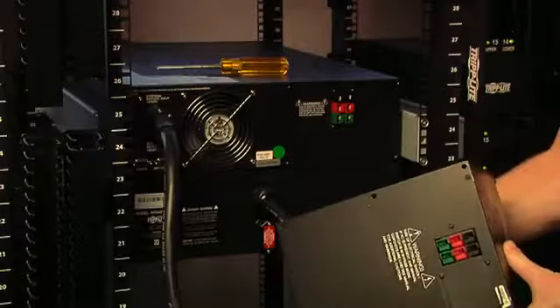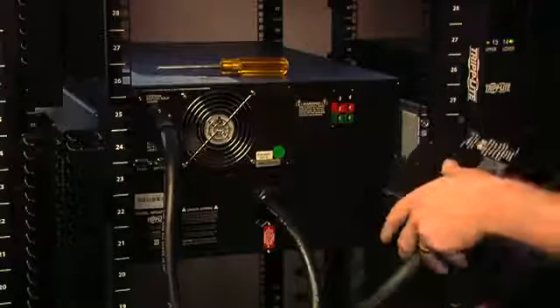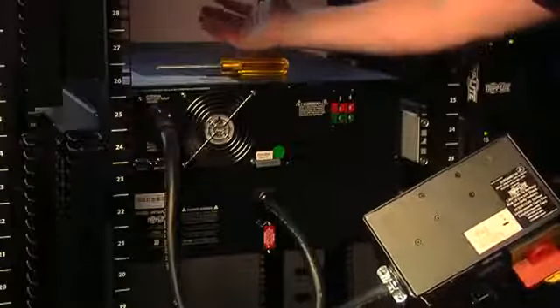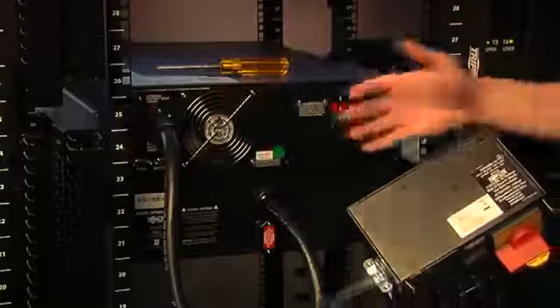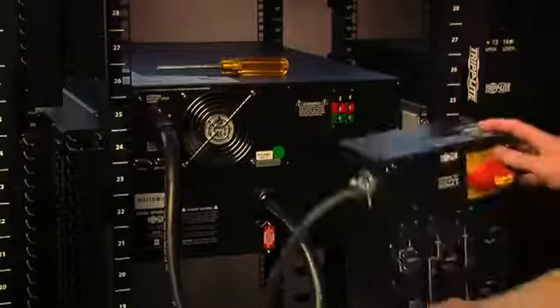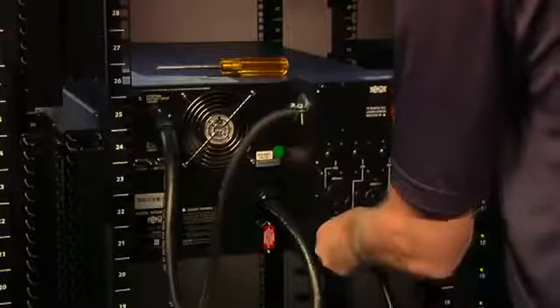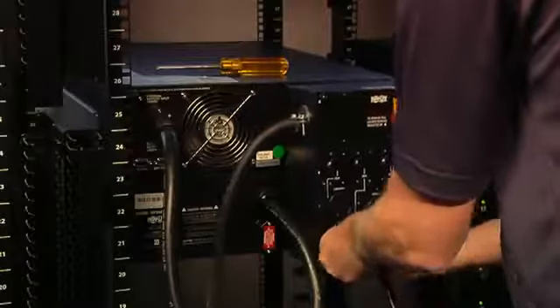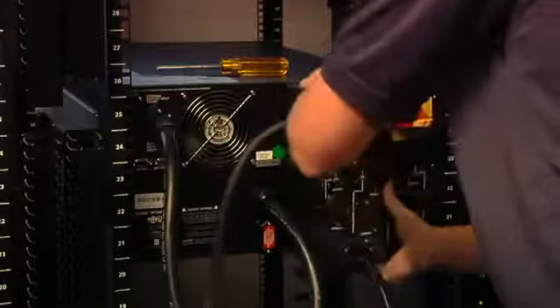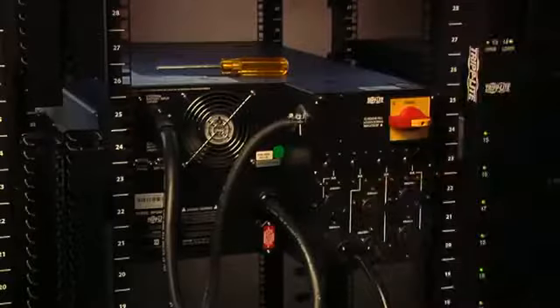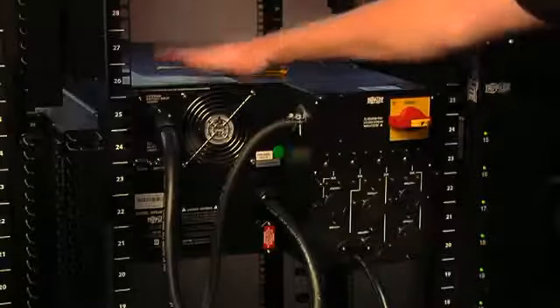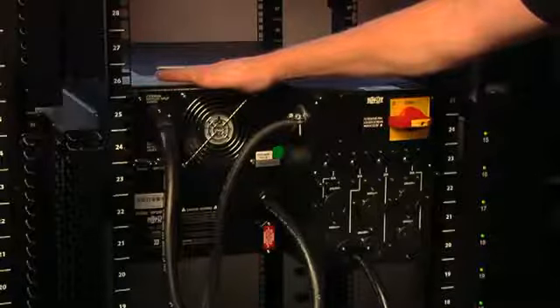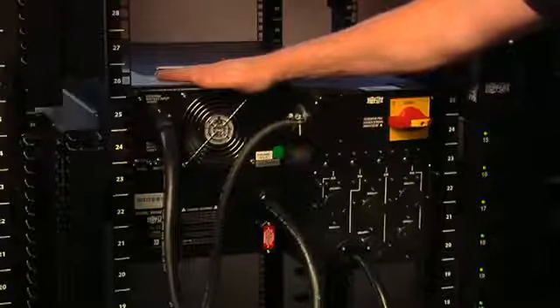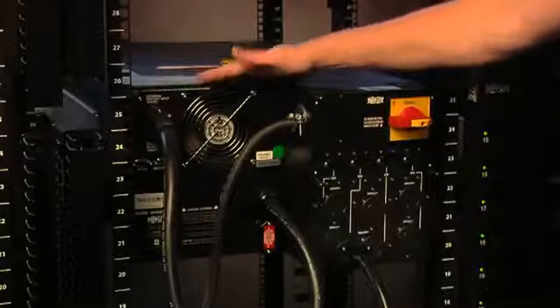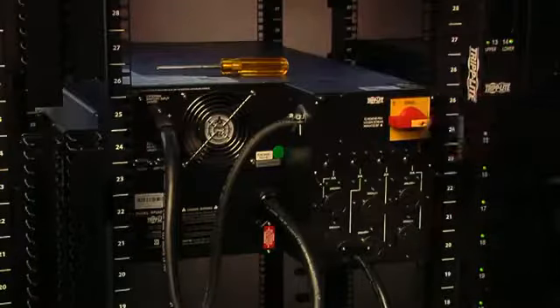Here you can see all of the input-output connections that mate with the power module. Okay, I can now remove the power module, reinstall a new power module while my loads remain powered. Once that's done, I reseat the power module, power distribution unit. Okay, now with a new power module installed, I need to turn it on and have it go through its diagnostic mode before I'm ready to shift the load back to a normal position.